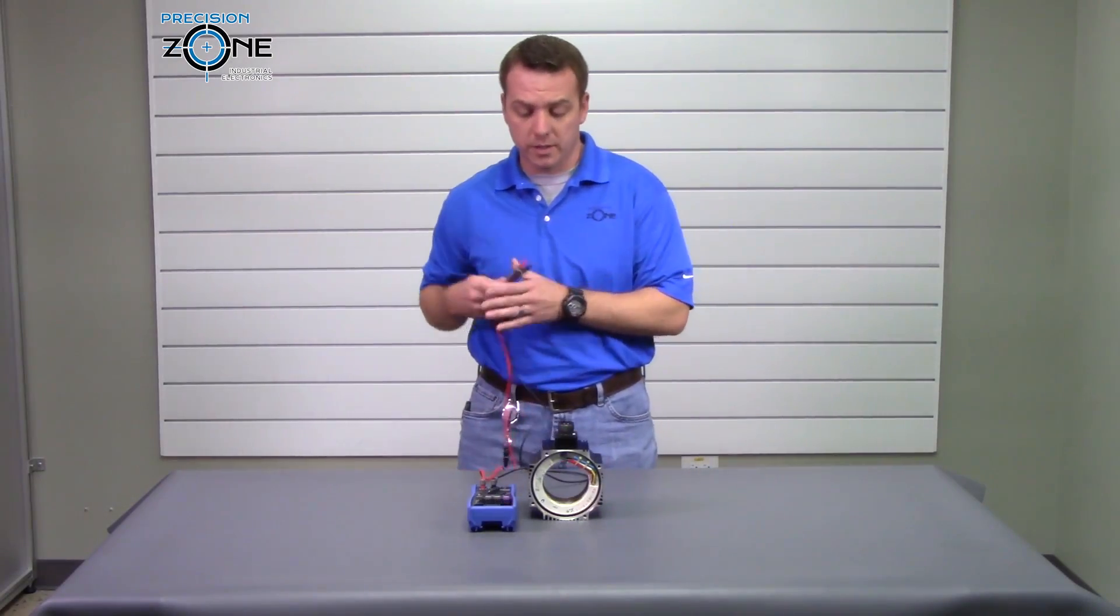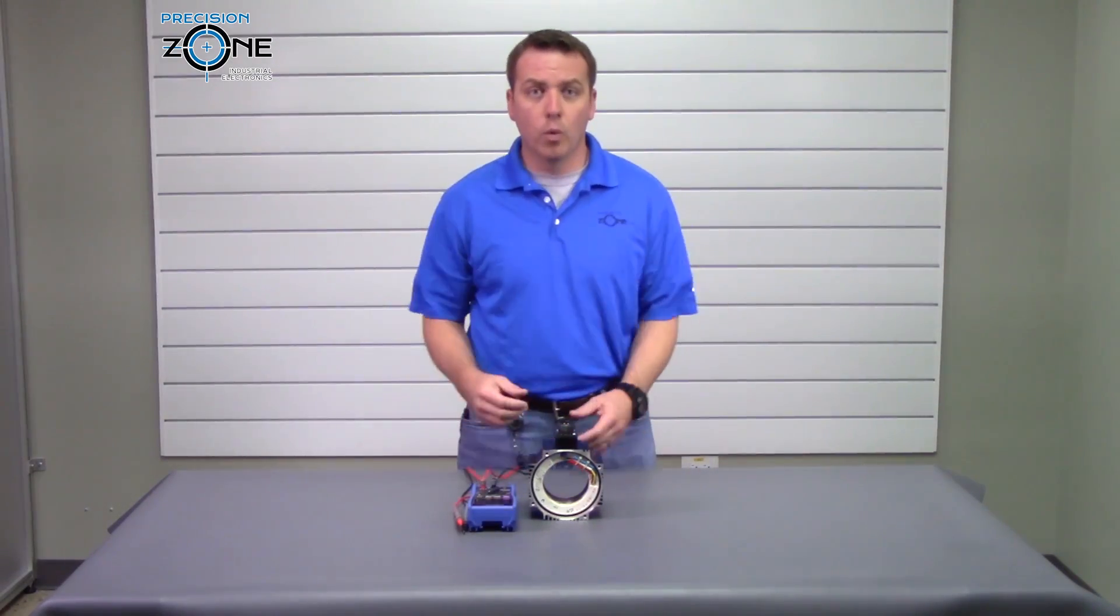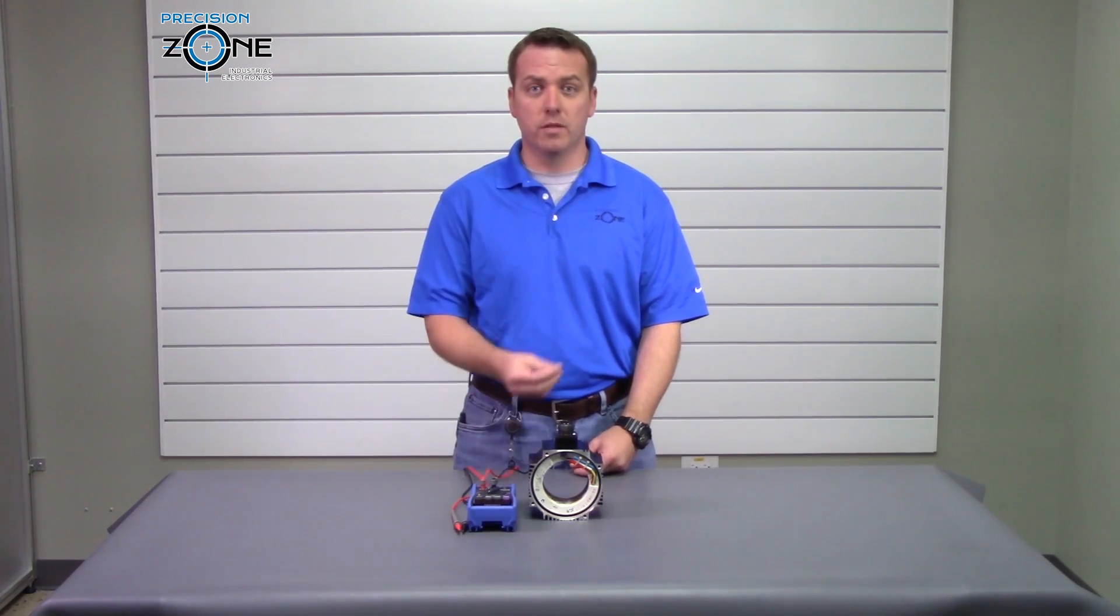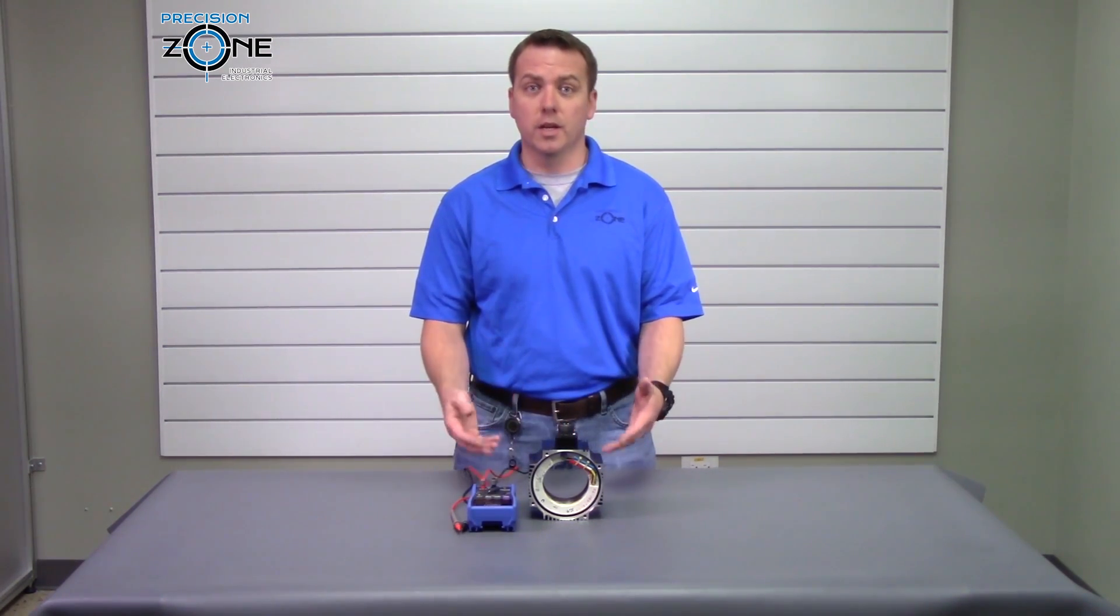Now I know specifically this stator should have about 1.05 ohms between the phases so there's obviously a problem.